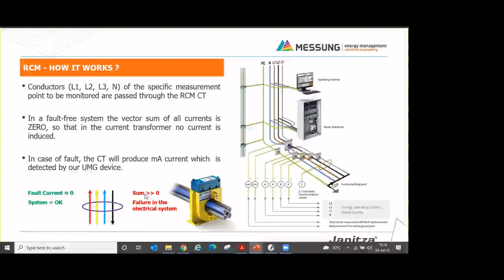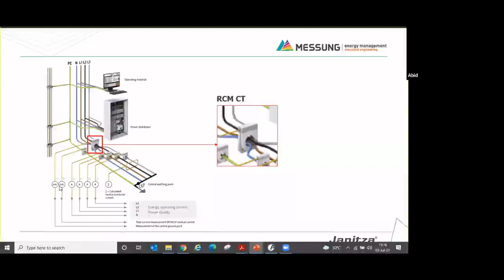Now this is the actual location, meaning this is how the CBCT is installed. All the phase conductors and neutral conductor are passed through it. And it gives the output which is in milliampere. So these CTs are basically rated for milliampere ratings.